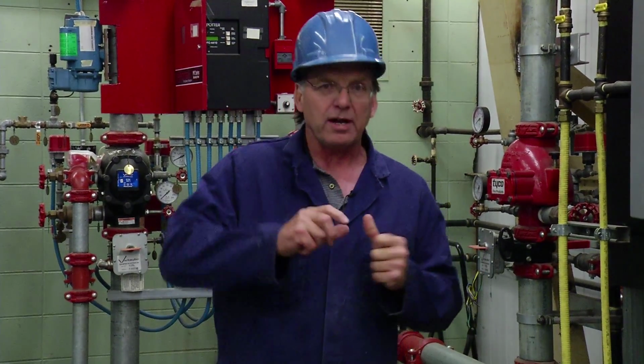All four of these units basically use the same recovery of latent heat that most condensing units do. That gives us that extra 10% efficiency, and it comes from the combustion process. The other interesting thing that these can do, and it's the newer technology, is that we can change the input in terms of how much gas they're burning and how much heat they're producing. This would be on demand. So in the old days when we had on-demand heaters, if you opened up your tap, you would fire them and you would get a one-stage heat. If you put too much water through your system, the temperature would just go down and down and down. So you had a minimum flow rate. Today, with the new technologies, as you open up more flow, these will ramp up the amount of gas they're burning and give you the set point temperature that you need.